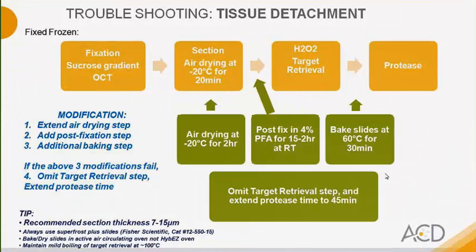So if you have a tissue falling off issue with fixed frozen samples, here are the 3 recommendations we give customers. The first one, you can extend the air drying step up to 2 hours, or add a post-fixation step after air drying. The post-fixation step can be 15 minutes to 2 hours. And then also add an additional baking step after target retrieval. So if all 3 recommendations have failed, you can also try to skip the target retrieval step and extend the protease time from 30 minutes to 45 minutes.